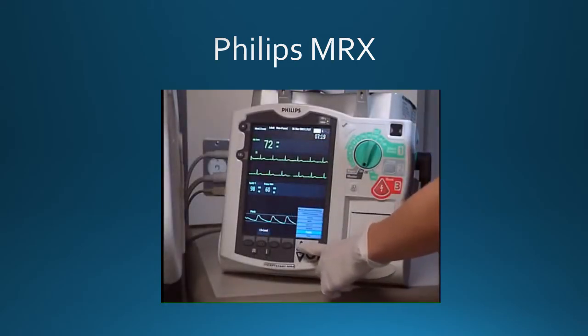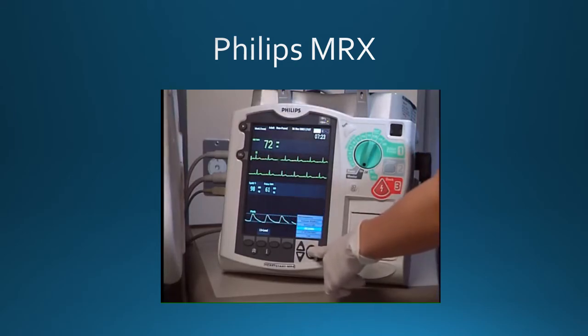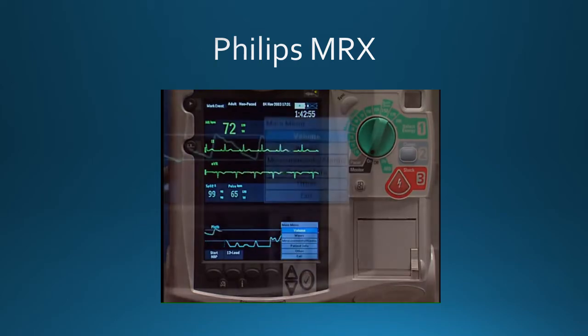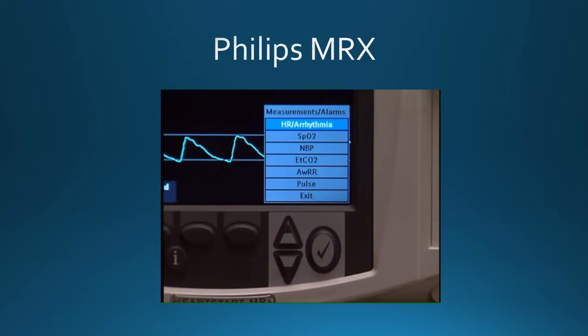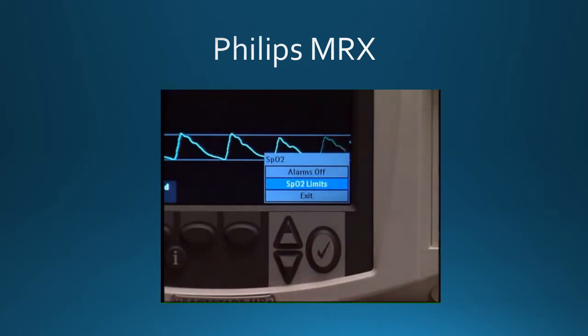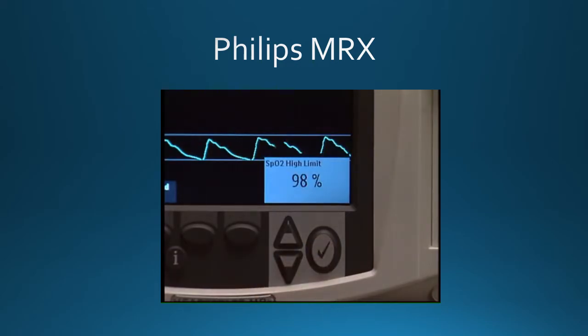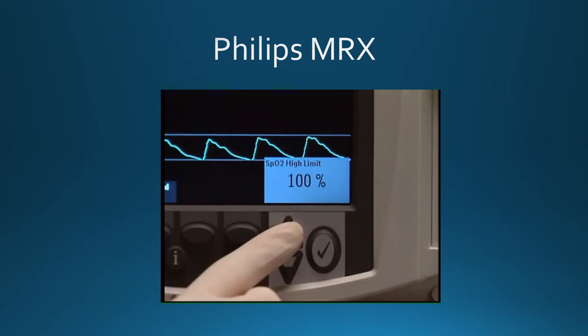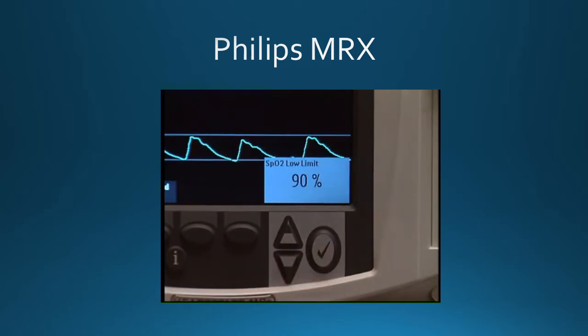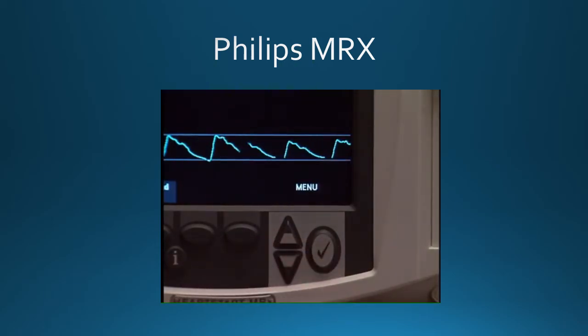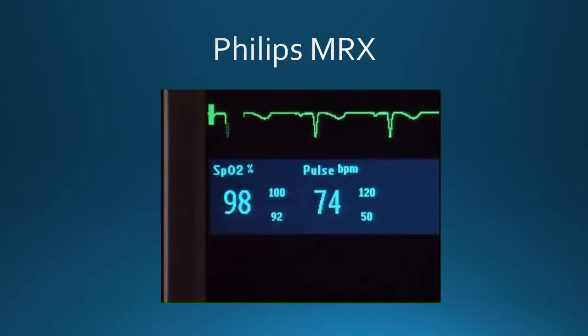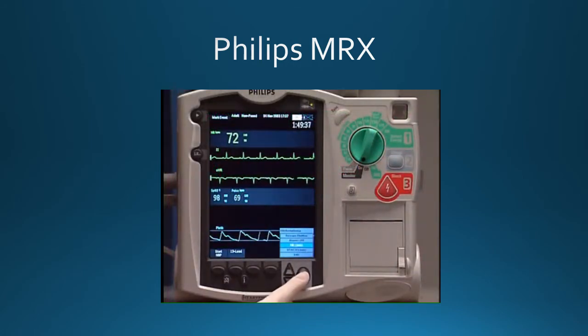Setting high and low alarm limits and turning alarms on or off is the same for all measurements, so let's look at how to do these tasks using pulse and SpO2 as examples. To set the high and low limits, press the menu select button. Navigate to Measurements, Alarms, SpO2, and SpO2 Limits. The high limit appears in this window. Use the up or down navigation buttons to increase or decrease the high limit. Press Menu Select to set the new high limit. Now the low limit appears. Use the navigation buttons again to adjust the low limit and press Menu Select to set the new low limit. The current high and low limits for each measurement appear next to its measurement numeric. Setting the high and low alarm limits for other monitoring parameters is similar to what you've just seen.